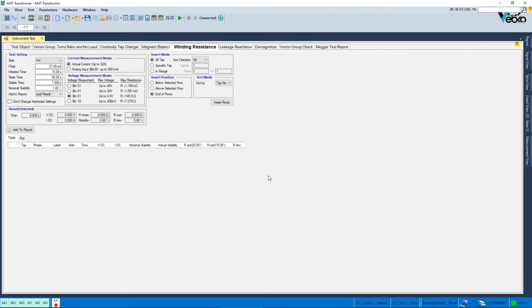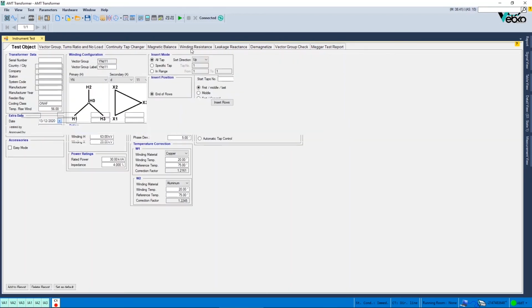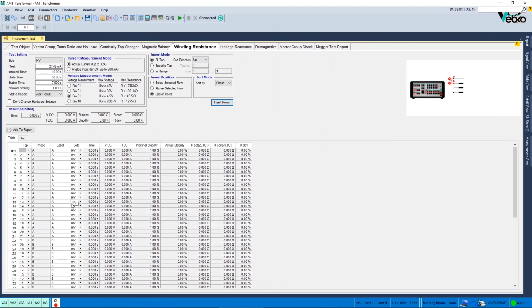Another one of the most important options of the software, which helps a lot in accelerating the test, is Sort Mode. Generally, for tap changer transformers, it is suggested that this option is set at phase. By doing so, it is possible to test all taps of a phase and then go to the next phase. But if tap number is selected, first you need to measure the resistance of all 3 phases and then change the tap. For example, suppose that your transformer has 21 taps. By setting Sort Mode at phase and selecting Insert Rows, you can see that the rows are arranged according to the selected phase, which helps a lot to increase the speed of the test.